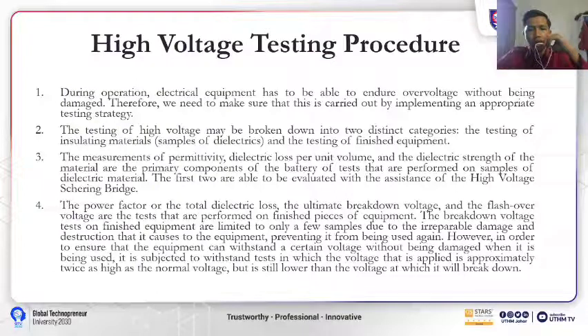The first two can be evaluated with the assistance of a high voltage Schering bridge. And last, the power factor or total dielectric loss, the ultimate breakdown voltage and the flashover voltage are the tests that are performed on the finished pieces of equipment. The breakdown voltage tests on finished equipment are limited to only a few samples due to the irreparable damage and destruction that is caused to the equipment, preventing it from being used again.